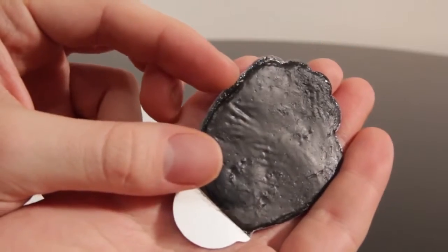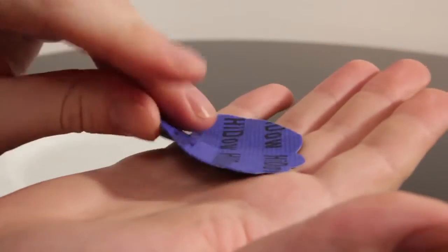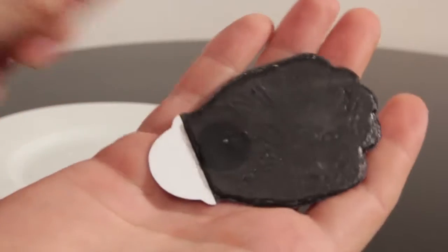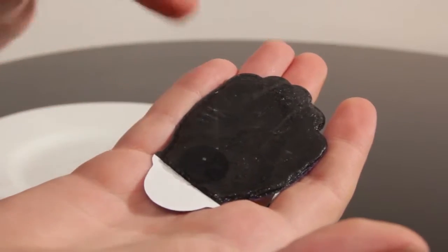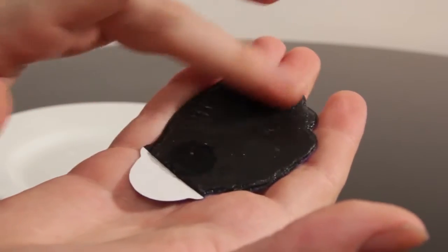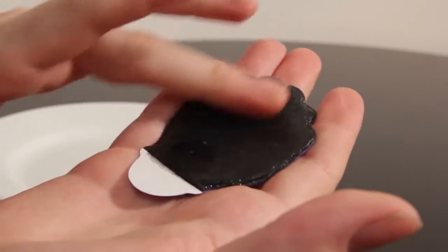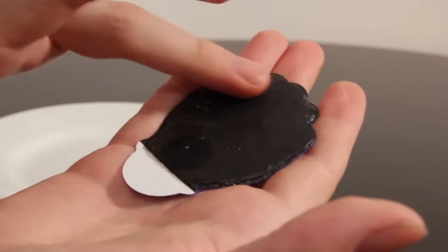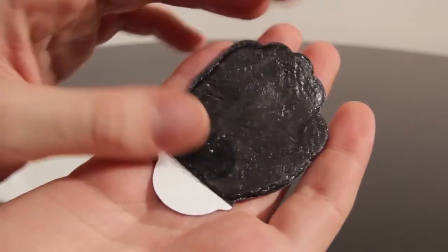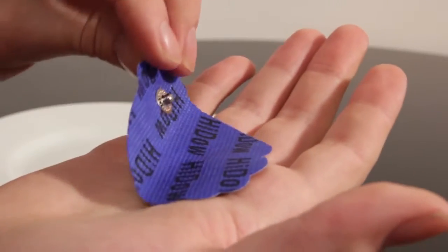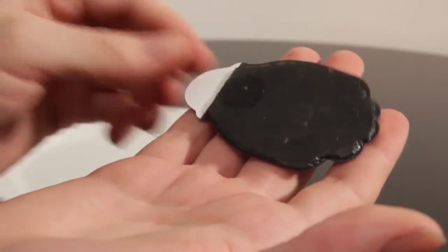After 4 or 5 applications, the gel on the self-adhesive electrodes will lose some of its adhesion. To rejuvenate the electrode, place a small amount of water onto the pad with your finger. Smear the water evenly. The water will be absorbed into the pad and rejuvenated, leaving it refreshed.